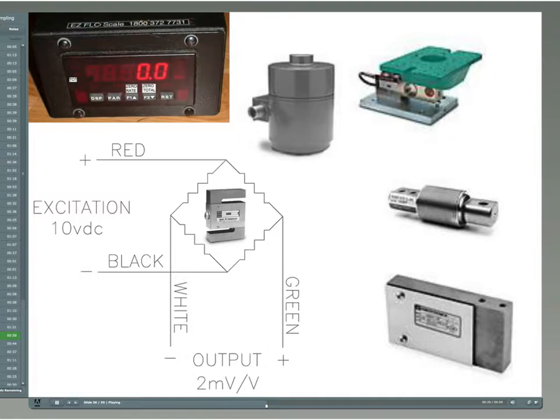The maximum load for a load cell is usually equal to 150% of its full-scale rating. The full-scale millivolt output is equal to the excitation voltage multiplied by the full-scale output sensitivity rating. With a 10 volts DC excitation input, a 2 millivolt per volt full-scale sensitivity rating, and a 10-pound full-scale load rating, the output ranges from 0 millivolts DC to 20 millivolts DC, as the applied load ranges from 0 pounds to 10 pounds.